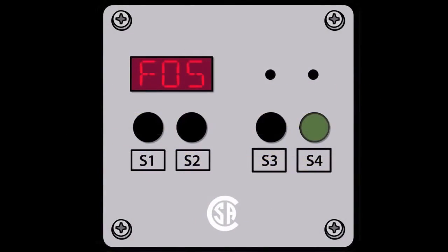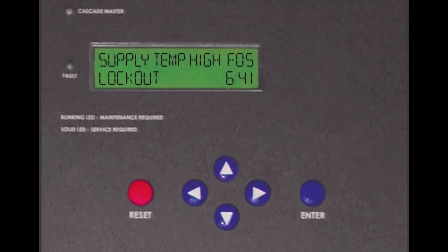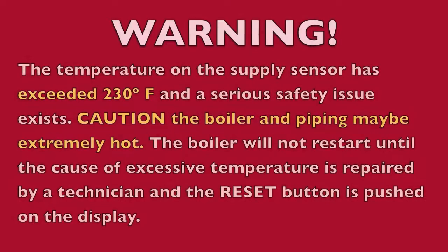If you are getting an F05 code in the display, this indicates that the supply temperature has been exceeded above its safety limit of 230 degrees F. Be careful before proceeding as the piping and the boiler may be extremely hot.